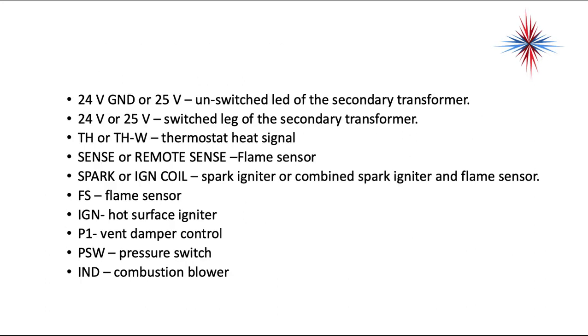24-volt ground, 25-volt ground is an unswitched lead off the secondary transformer. 24V, 25V is the switched leg of the secondary transformer. THW is the thermostat heat signal. Sense or remote sensor is the flame sensor. Spark or ignition coil, spark igniter, is a combination spark igniter and flame sensor. FS is the flame sensor. IGN would be a hot surface igniter. P1 would be to a vent damper control. PSW would be to a pressure switch. IND would be to a combustion blower.